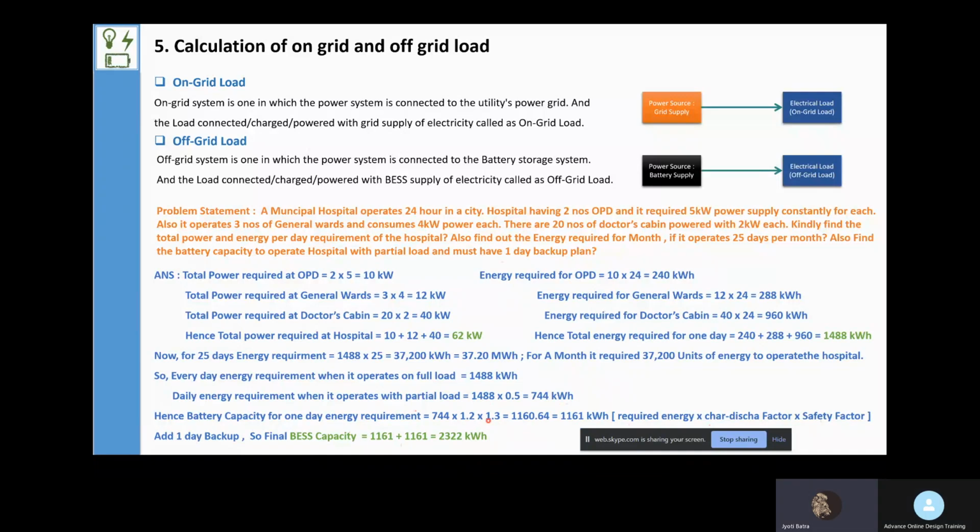Is there any thumb rule fixed for BESS capacity? You can treat this as a thumb rule, but it may vary based on the application and the battery chemistry. Roughly you can use this, approximately 60% to 70%. If you want, let's say, storage of 100 units for the required outcome, then you can put a battery pack of, let's say, a capacity of 130 or 140 kWh. Then you can easily draw out the 100 units from that. That would be the thumb rule.